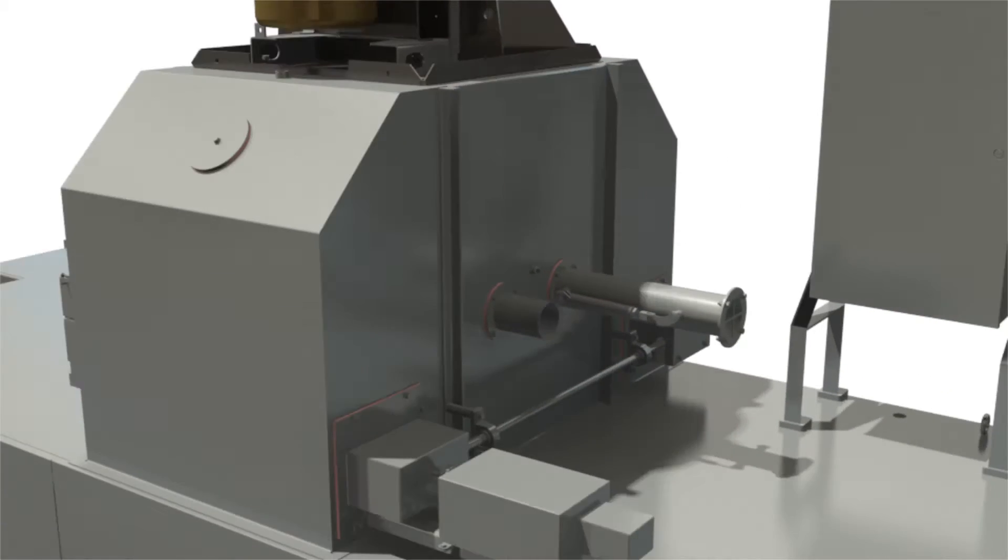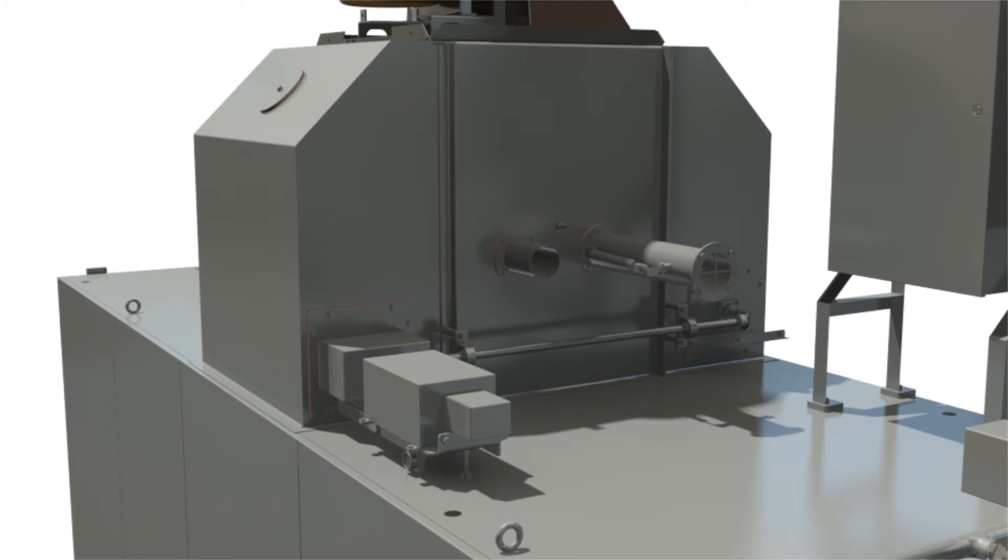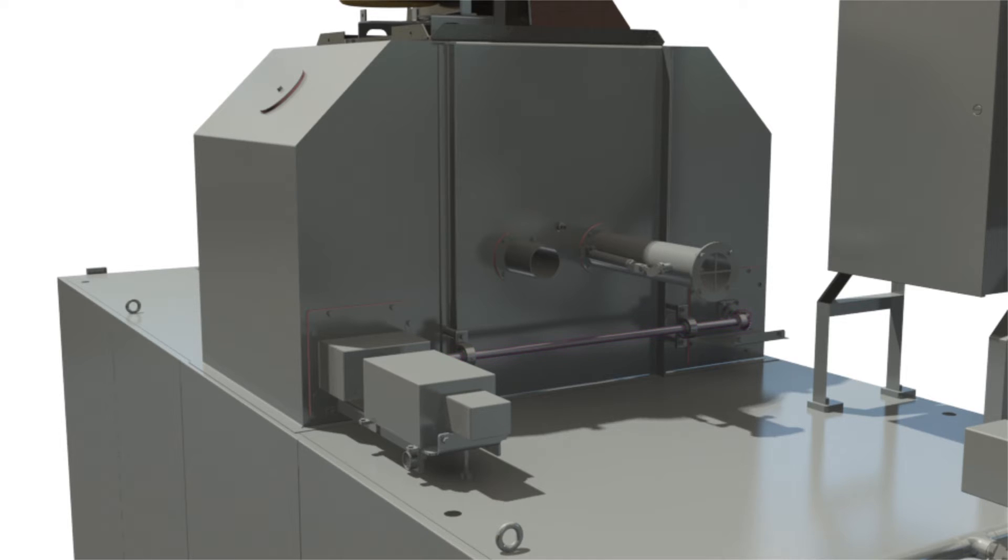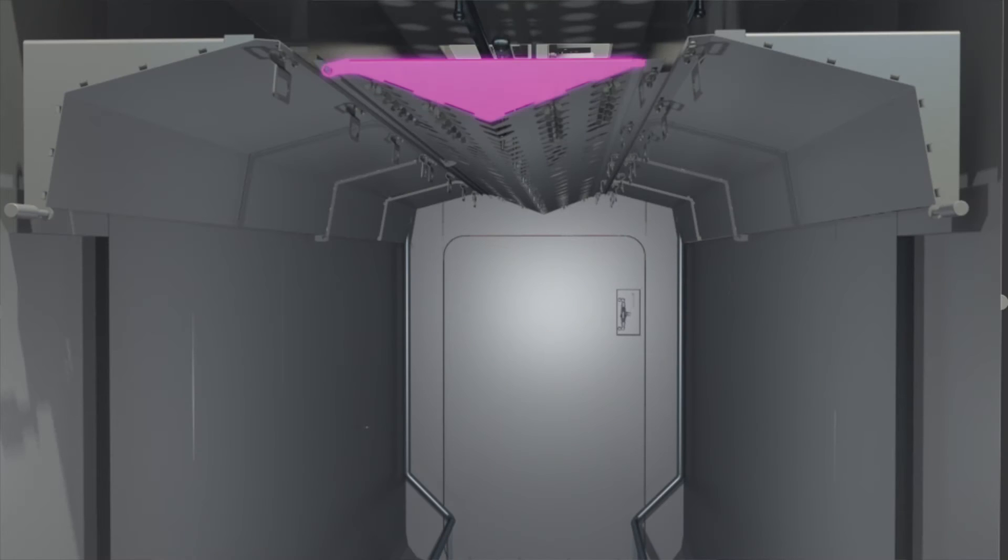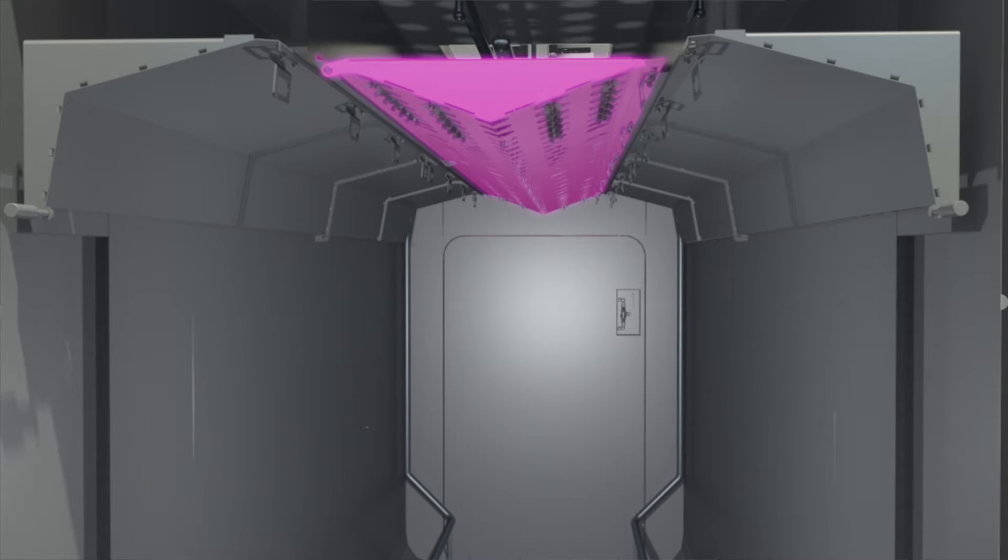The dampers are positioned and controlled together with a jack shaft system, keeping them in tune with each other, unlike the typical chain system that often goes out of alignment. The V-shaped or lowered return duct lessens turbulence and air rotation in the oven, creating an efficient return of air.